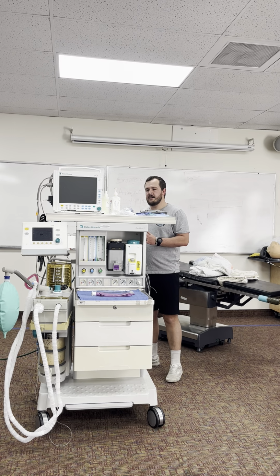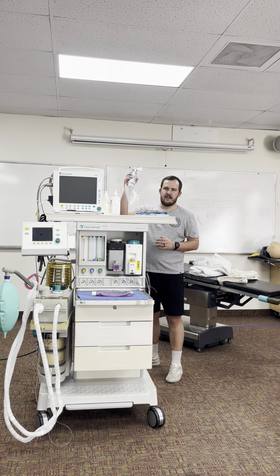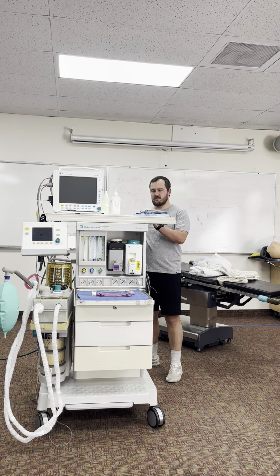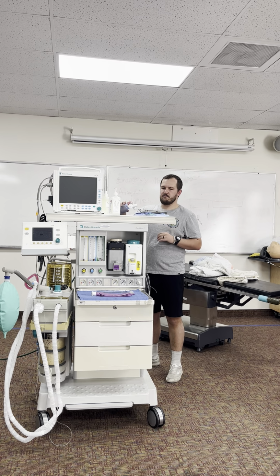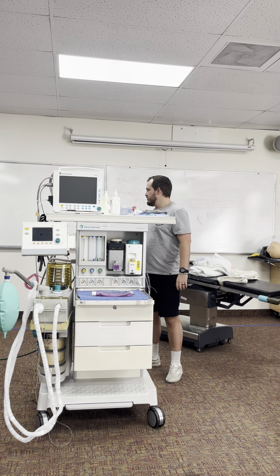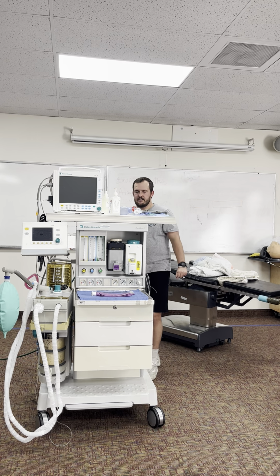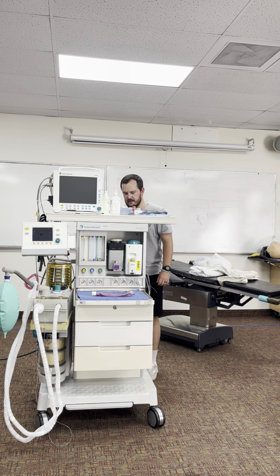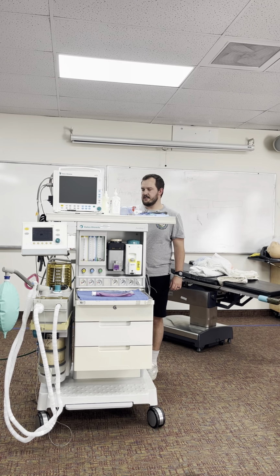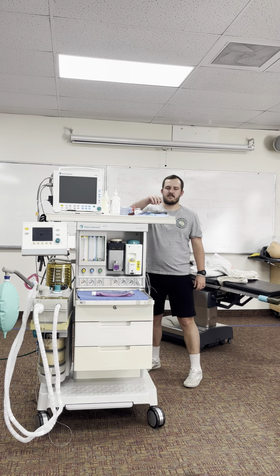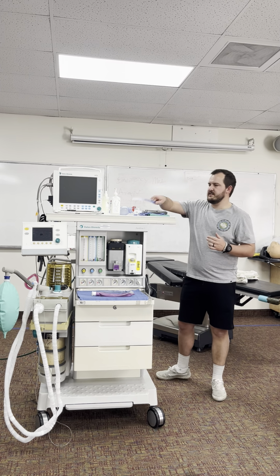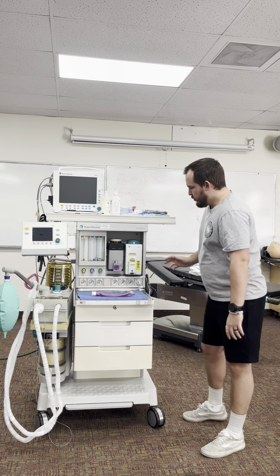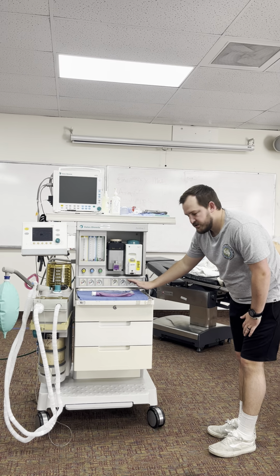And then since I'm back here, I'm going to just double check my ambu bag, make sure that it works, and that when I apply pressure, it does have some PEEP. It looks good. I'm going to check, make sure that my pipeline is secure in the wall, and then also that my pipeline supply is good into the machine. Since I'm still back here, I'll hook up my suction to the wall, turn it on, make sure it's appropriate, which it is. I'm going to come forward, I'm going to look at my pressures.